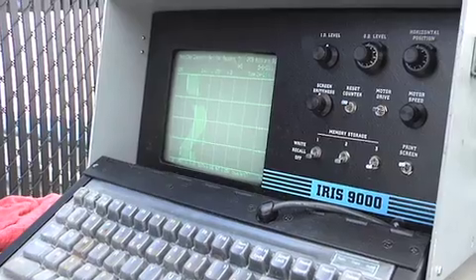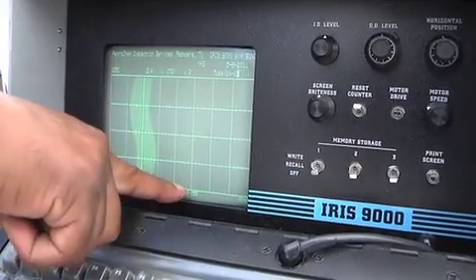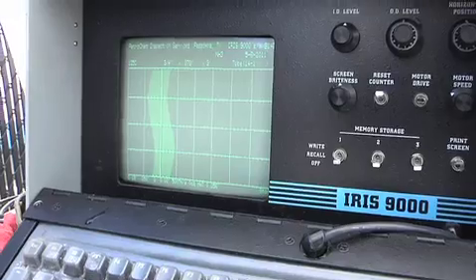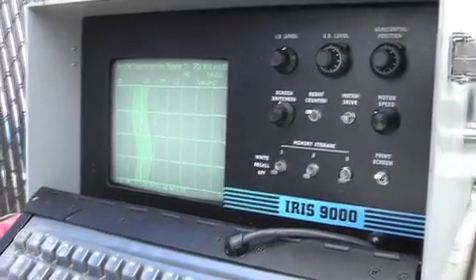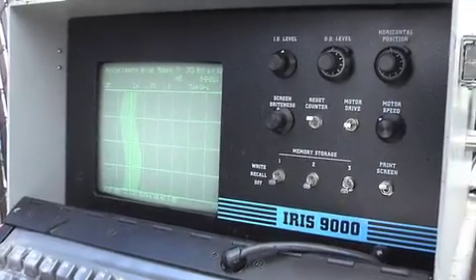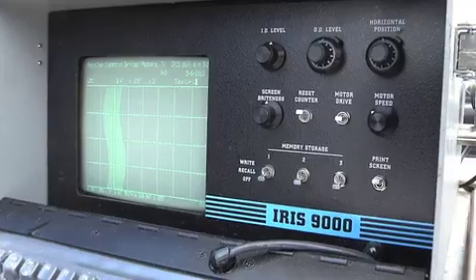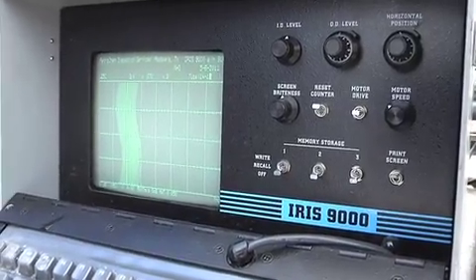This is a defect area. This is my measurements. This is my actual wall measure. This is the actual thickness of the tube in that 360-degree wall-loss area as I continue to pull.